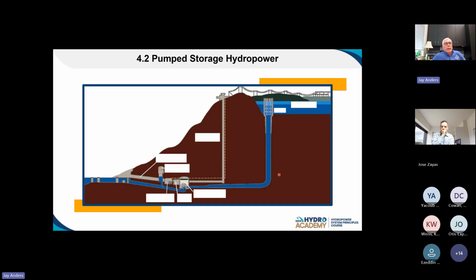One thing I'd mention, going to this next drawing - something people unfamiliar with this may not know is that when we build these, there's one generator/motor, a three-phase motor, and that's what we're all operating on. It's all three-phase. What you end up doing is taking that one motor/generator and swapping any two phases in the motor, and by swapping two phases it rotates in the opposite direction. Once it operates in the opposite direction, you've basically turned a turbine into a motor.